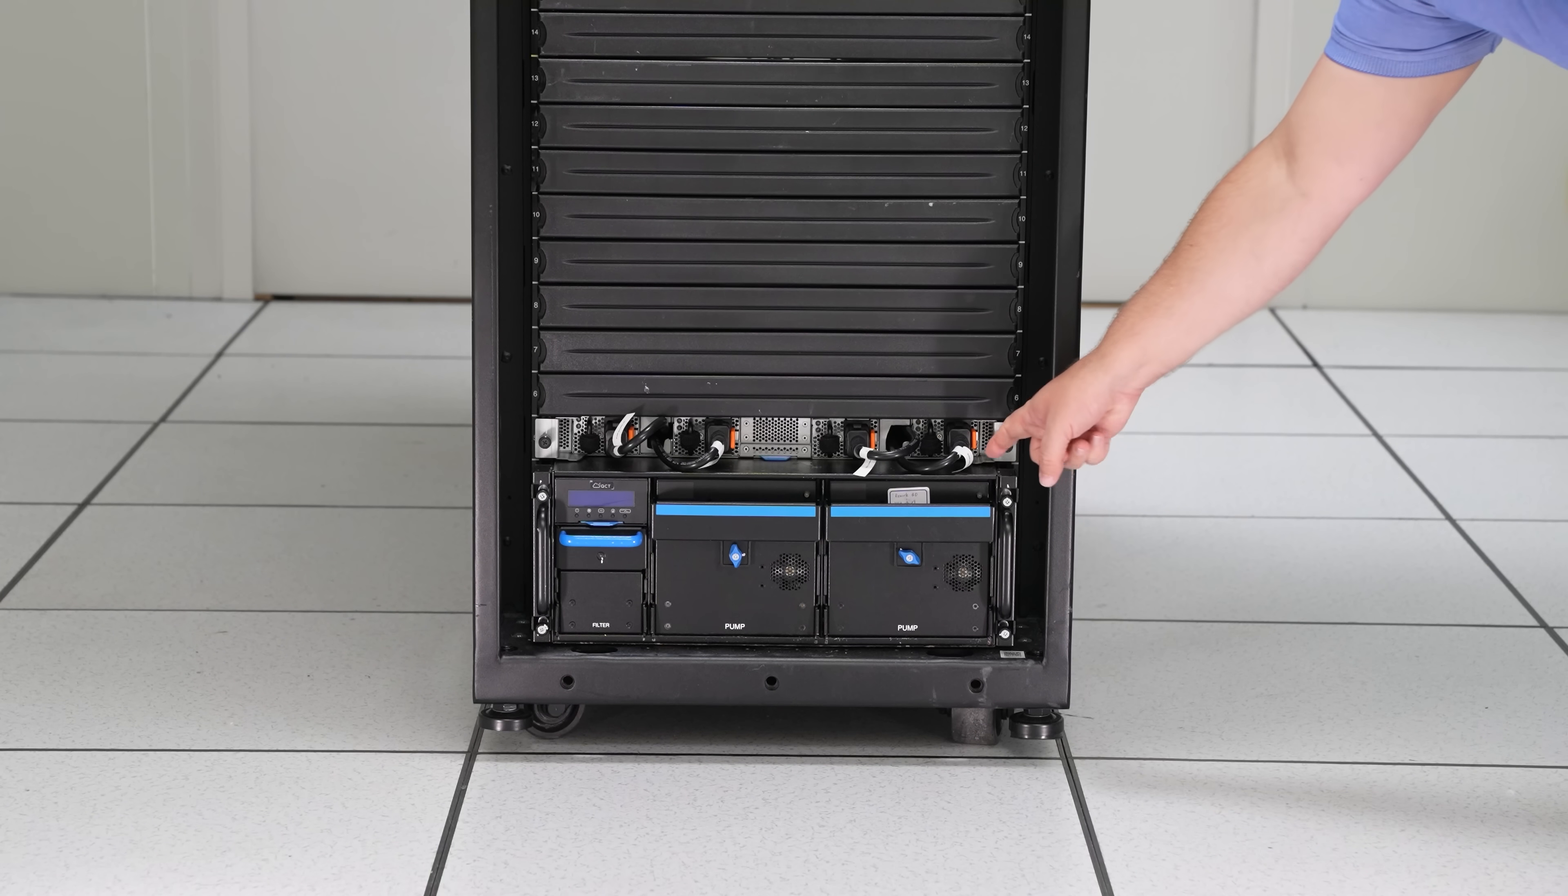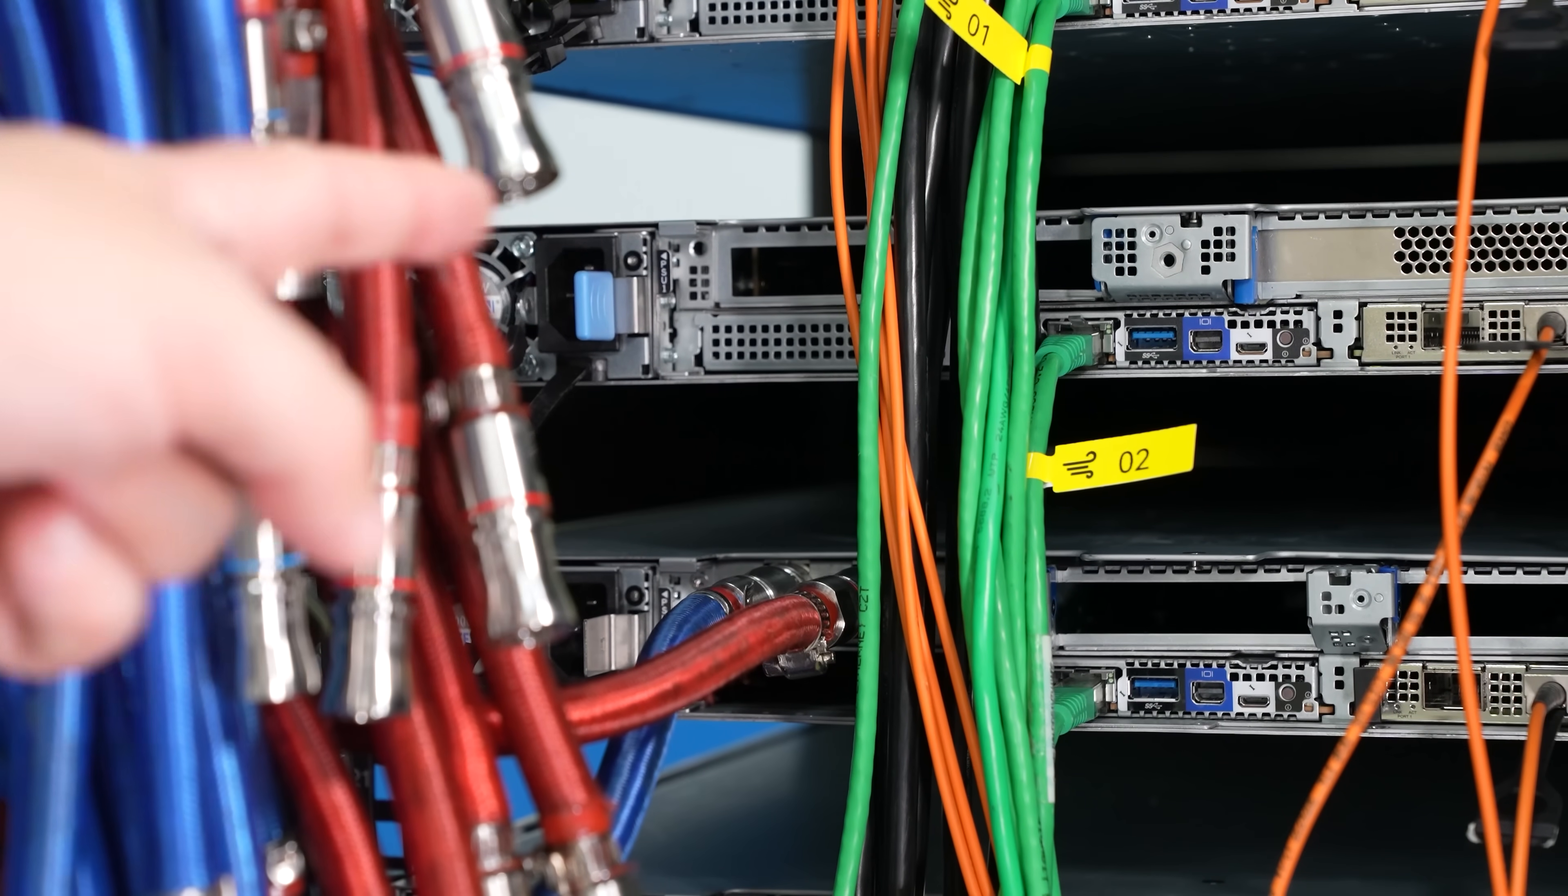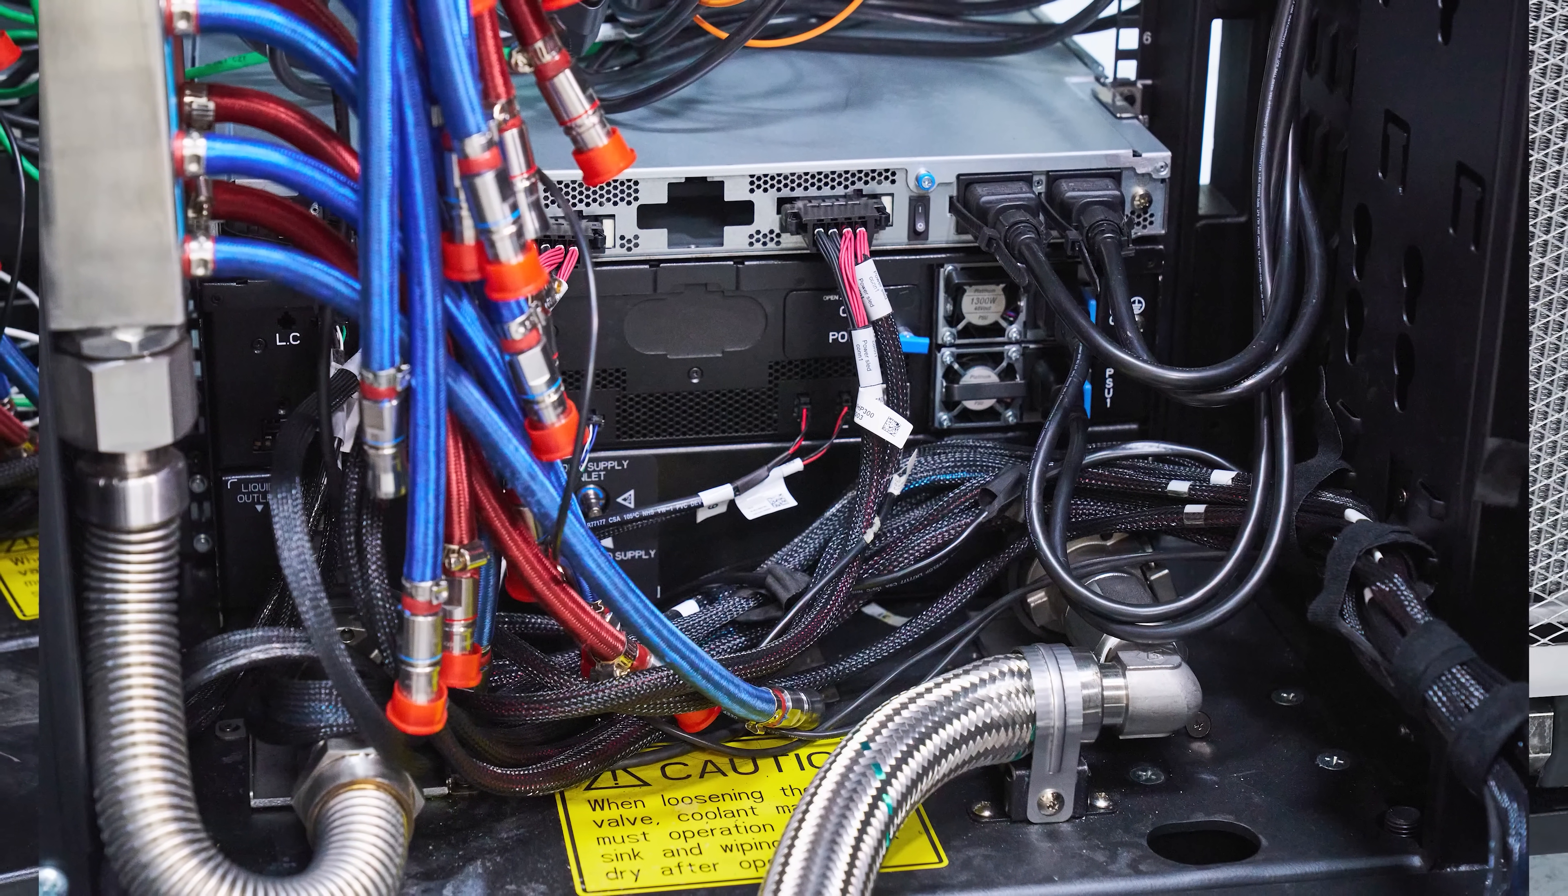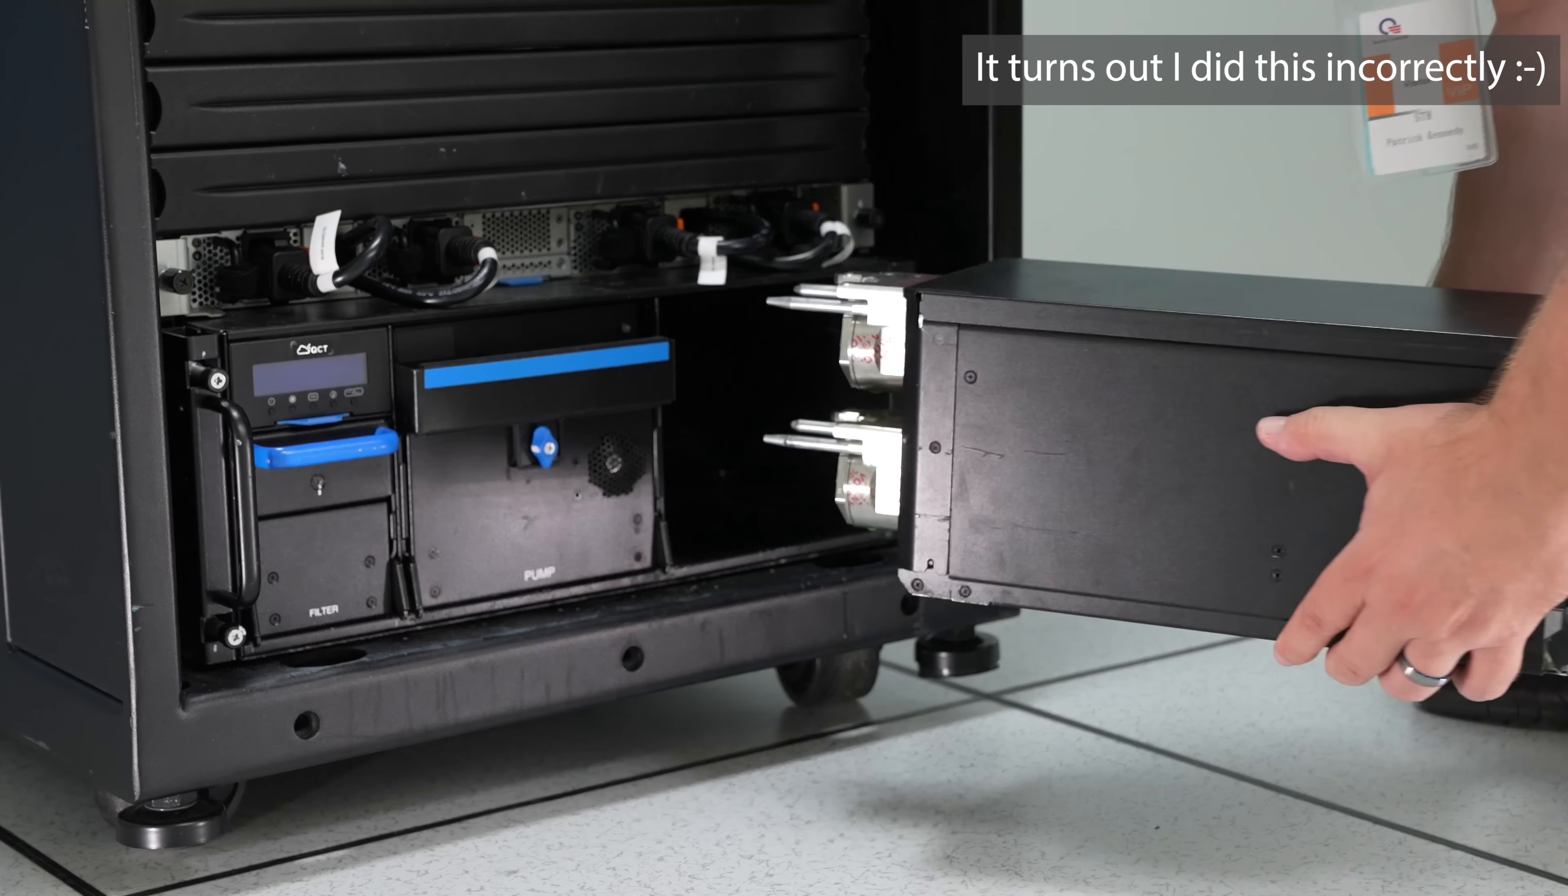Now, if you go to the bottom of the rack, you will see a CDU, or cooling distribution unit. Now, if you haven't seen STH videos on liquid cooling in data centers before, what a CDU does is it has a loop, and there's a loop that goes through the entire rack, and that is really there to go and cool all of the servers in the rack. However, you have a lot of heat that builds up or it gets transferred from the servers into that liquid cooling loop, and so you need to get rid of that heat, and the way you do that is with a CDU. The CDU does a heat exchange between the loop that's in the rack and then some kind of facility water.